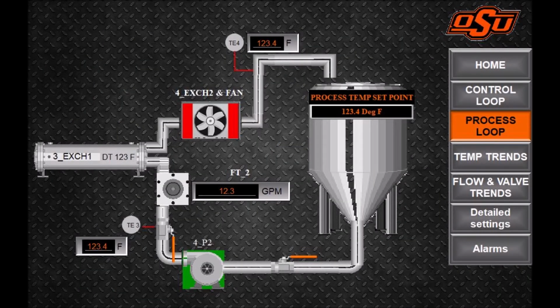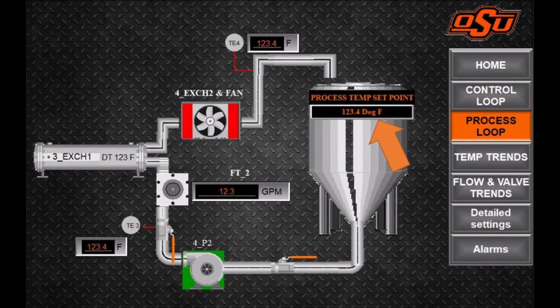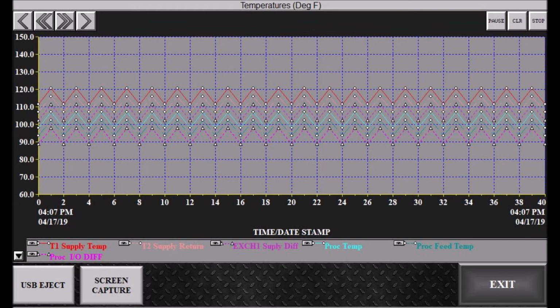In the process loop screen, the process fluid runs through the heat exchanger and into the tank. A pump then pushes that fluid back into the heat exchanger. On this screen, the operator can also view the temperature of the fluid. The temperature elements are measuring the temperature in the tank as well as after the radiator. The other flow indicator is positioned after the pump. The temperature set point of the tank can be selected by pressing on the process temp set point. This value will be updated in the PLC program. If the fluid is above the set point, the radiator fan will come on to cool the fluid. As we move to the trend screen, the temperature trend screen will allow the operator to view the trends in real time.